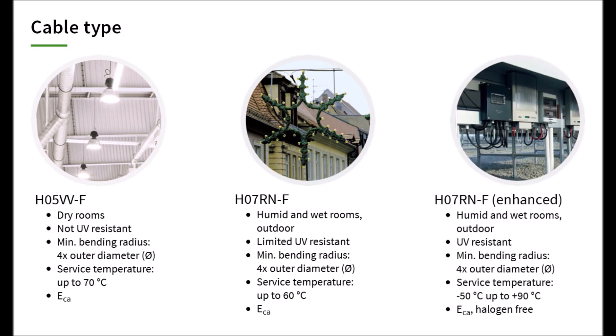Usually, little attention is paid to the maximum service temperature, which is the result of the ambient temperature plus the self-heating caused by the current flow. The H07RNF, the enhanced version, offers improved protection. For higher requirements, such as for shipbuilding or solar technology, the choice of a suitable cable or seal must be discussed with us.